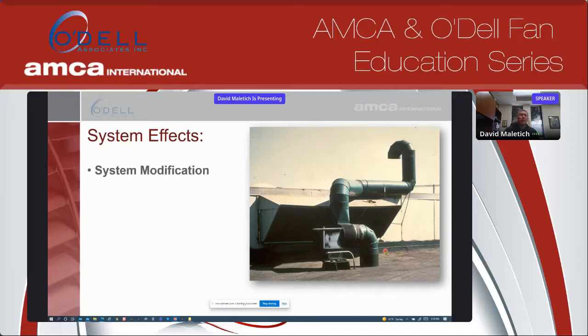Here's another modification. This fan here was moving lavatory or bathroom exhaust air out of the building. This is the clean air intake into the building just behind it. When employees were complaining about the smells getting back into the building, their engineering staff developed this little duct system to redirect the smells away from the clean air intake. However, they're going to have to speed up the fan because there's additional losses associated. You got this 90-degree elbow here, abrupt elbow here, and then 180-degree elbow at this point. You're going to have some system losses unless you speed up the fan. You're not going to be pulling stuff out of the lavatories like it originally was designed to do.